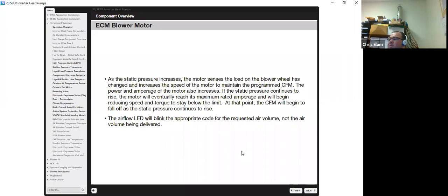If the static pressure continues to rise, the motor will eventually reach its maximum rated amperage and begin reducing its speed and torque to stay below that limit. That's what they call fallback. So at that point, the CFM will begin to fall off as the static pressure continues to rise. The airflow LED will blink the appropriate code for the requested air volume, not the air volume being delivered.